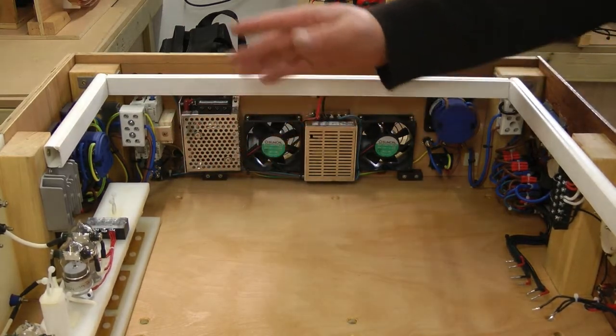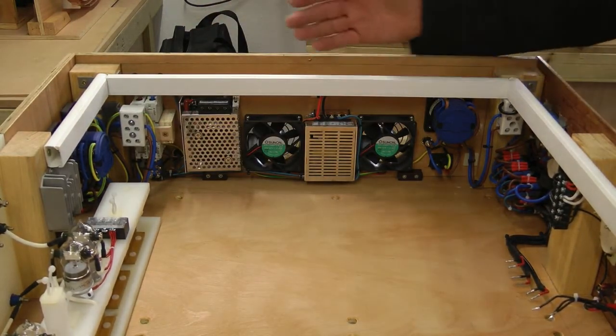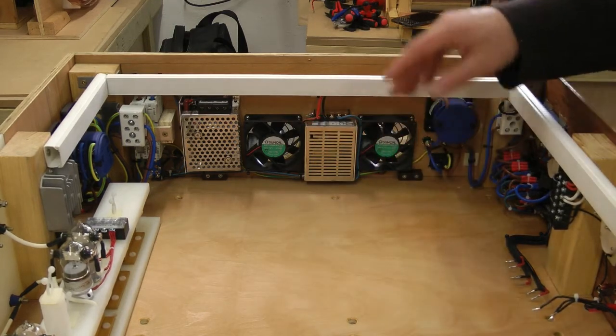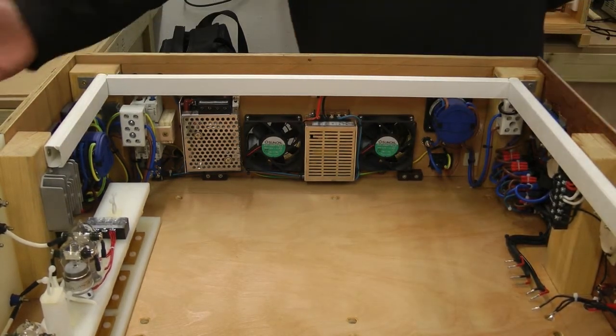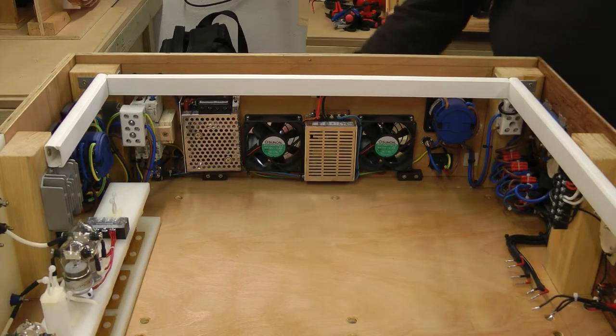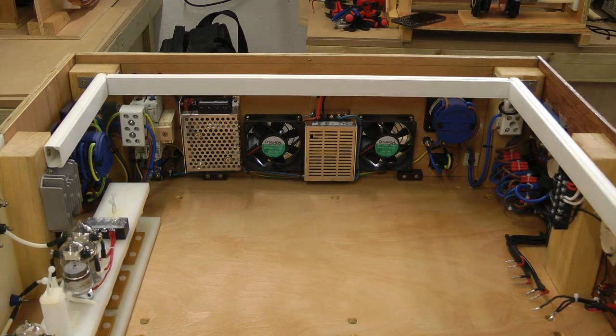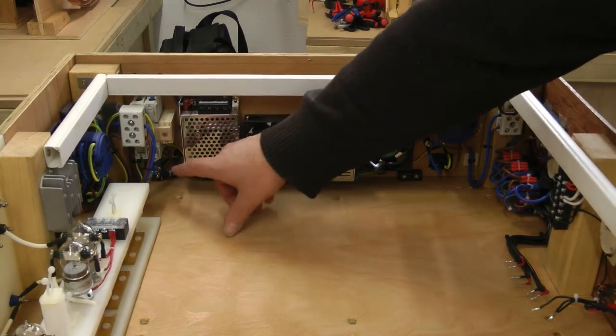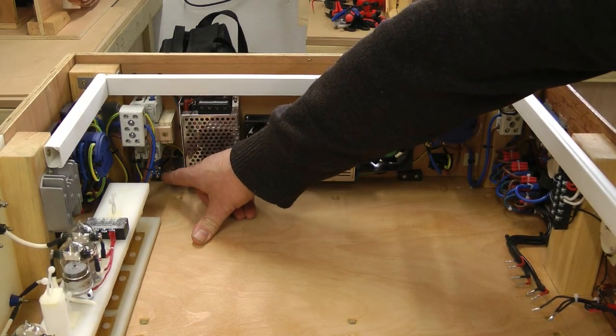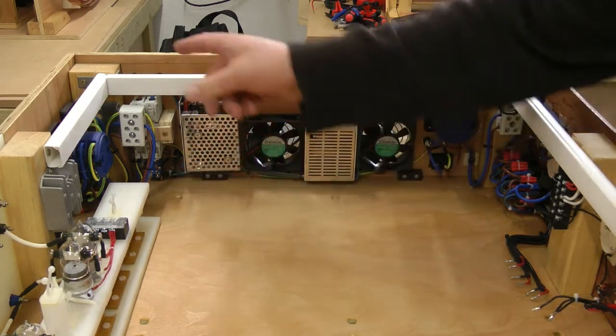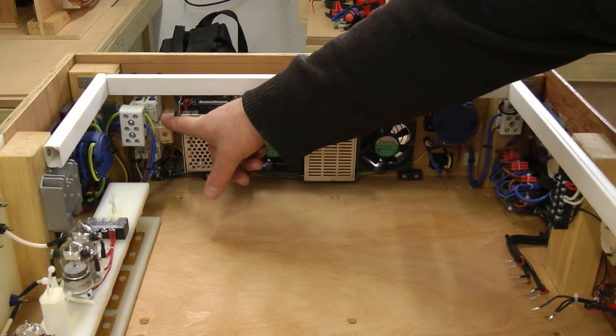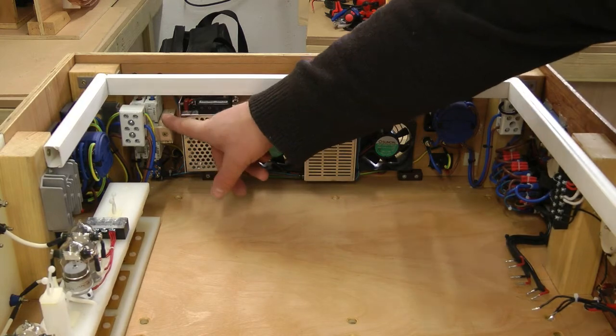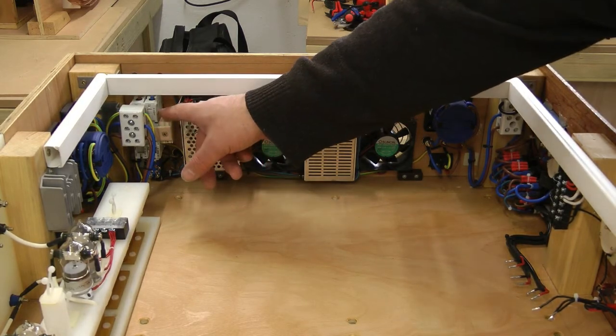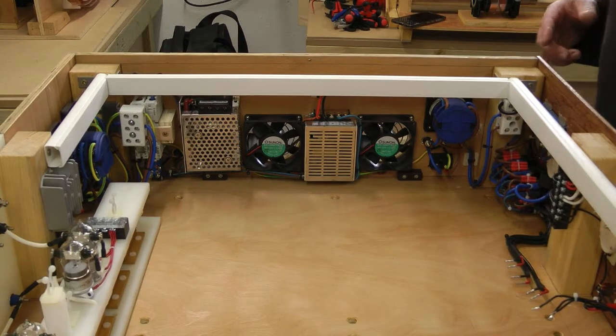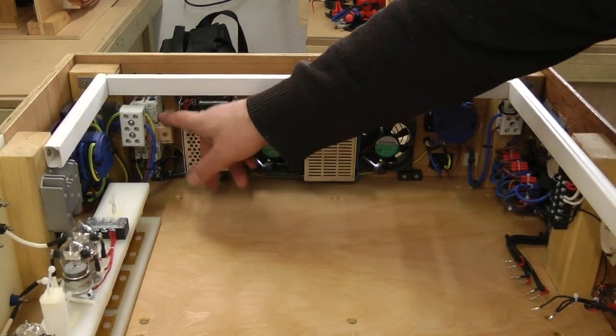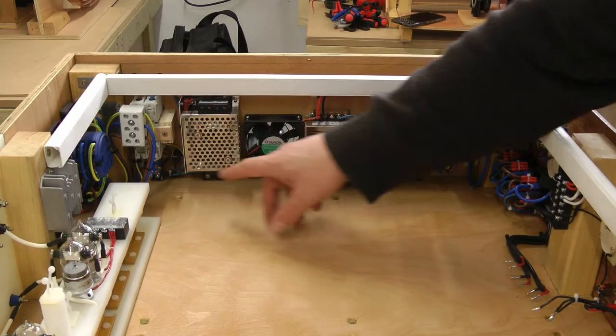Each of these panels is designed so they can fold out for easy work on them. So for example, this panel here would fold this way. This panel folds out this way, and the front panels fold out downwards. So low tension switching here, along with the fuse and the indicators at the top. There's a 32 amp double pole MCB on this side as well. That's obviously for the transformer line supply.